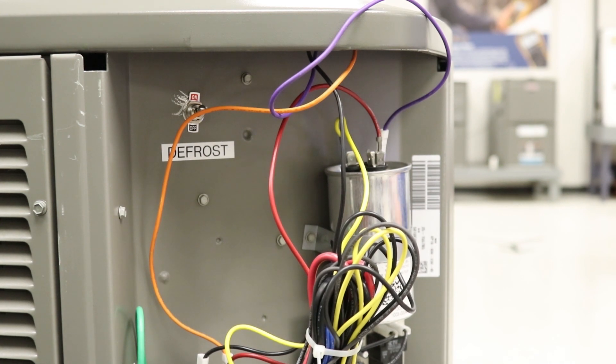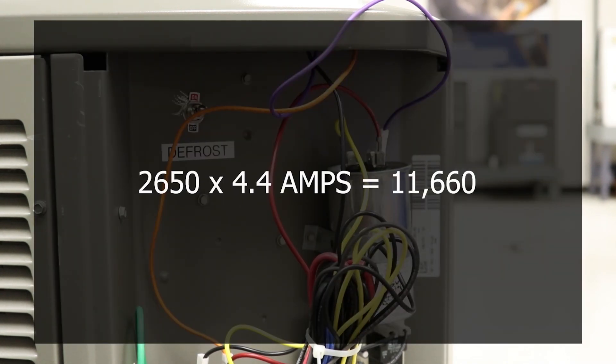Same thing for the hermetic side of things or the compressor side of things. We're going to take 2650, multiply it by the 4.4 amps that we had, which gives us 11,660.